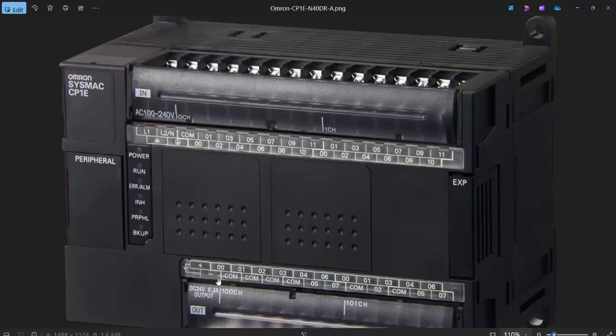Also you can choose the 24 volt output voltage of the PLC. Otherwise, if you would like to use an external voltage, that can also be used. So this is the minus voltage and this is the plus voltage. This minus voltage you can put at the common terminal, and this plus voltage you can use for your push buttons, meaning external inputs.